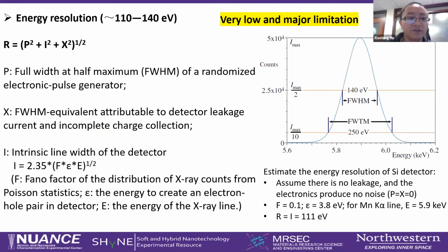Okay, so the next thing I will cover is energy resolution. Many people do not pay attention to this, but it is actually important. You need to understand that the resolution for EDS is very low, and this is a major limitation. So it's very possible that many peaks overlap with each other in your EDS, and that's why when you do the quantification, you need to pay special attention.